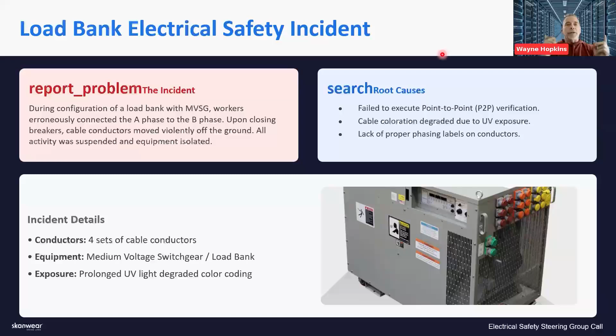During the root cause analysis, they determined that a point-to-point verification was not done. The cable conductors weren't confirmed to be A phase to A phase and B phase to B phase, etc.